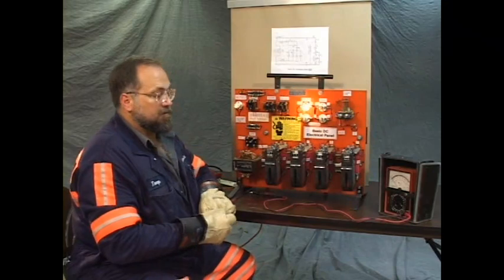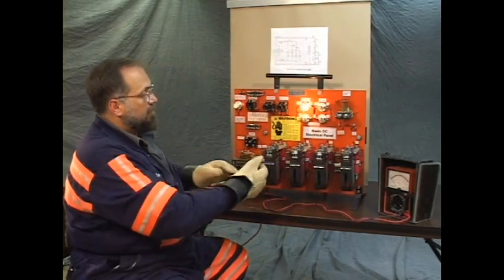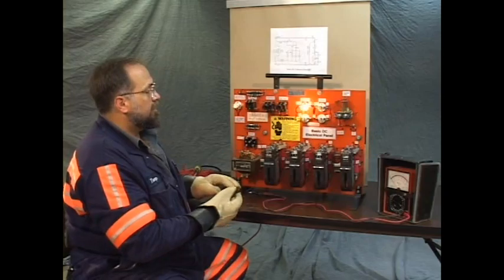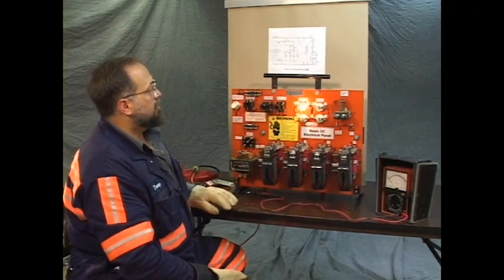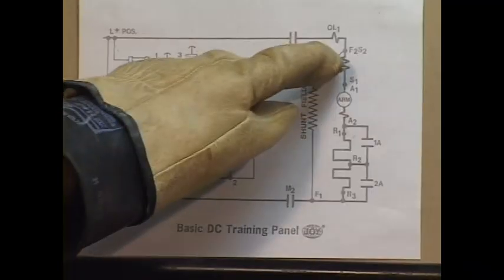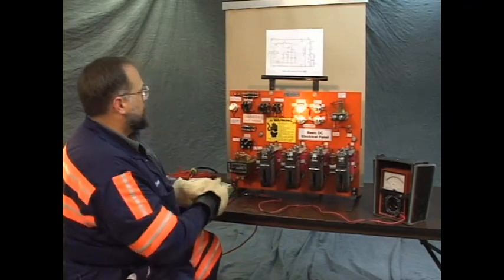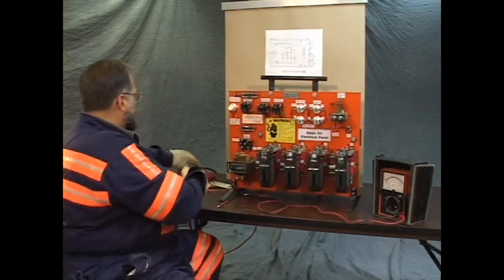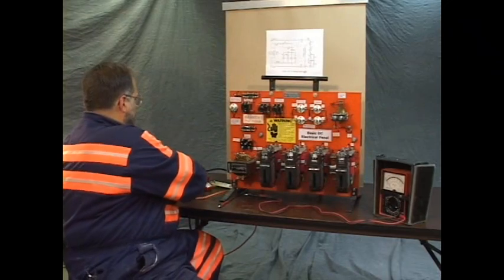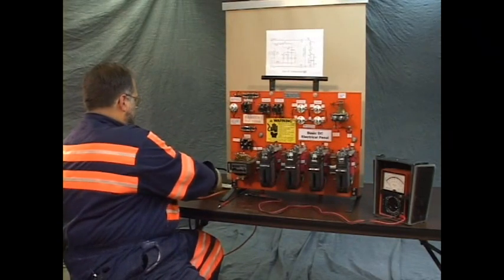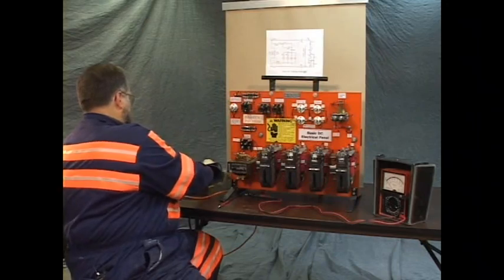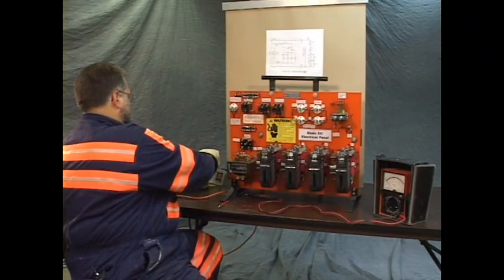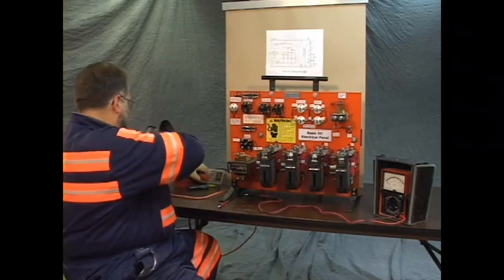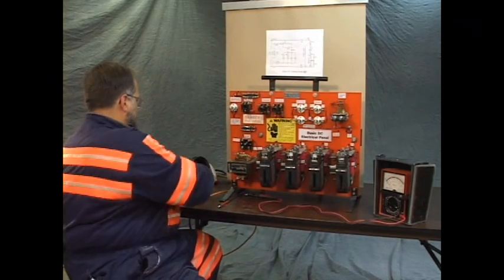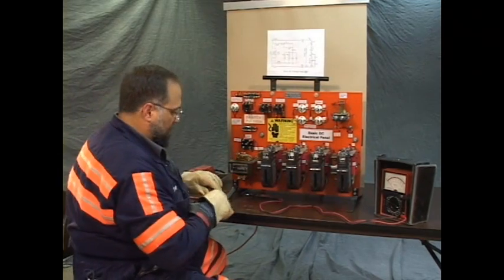By the fact the control circuit is operating, that tells us the contactors all closed in proper order. That tells us that this portion of the print, this portion of the circuit, is good. Our problem lies between this point and this point. So let's stop the panel, take the power off and lock and tag. Test to make sure that our power is indeed off. We're going to turn on our tracer.